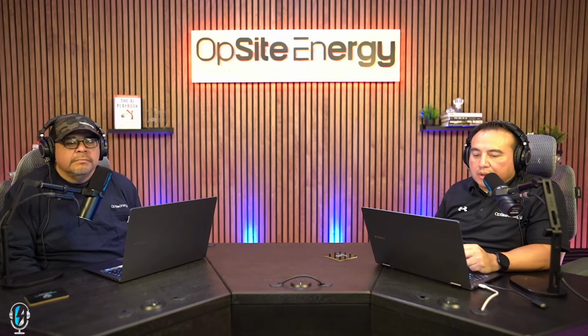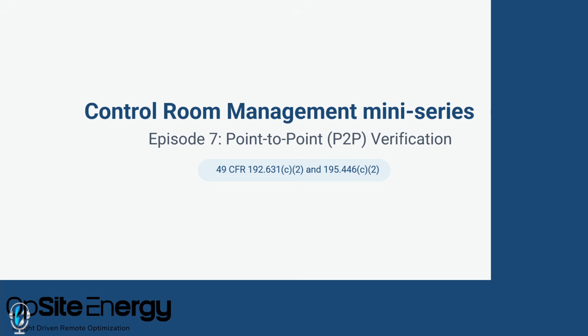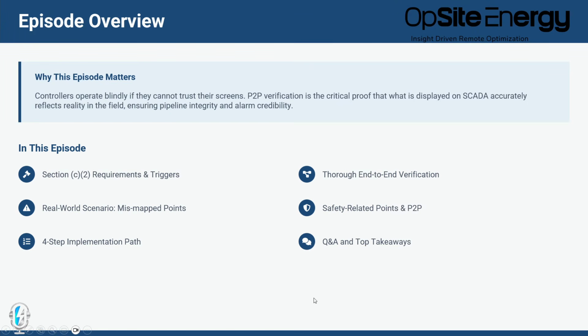Yeah, overall it's about the controllers making sure that the information being placed on the screen is something you can actually trust. That's what point-to-point verification is all about, making sure that your critical proof and what's being displayed on SCADA is accurate and reflects what's going on at the field level, to ensure pipeline integrity and alarm credibility.